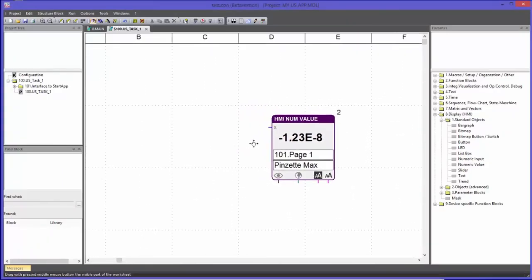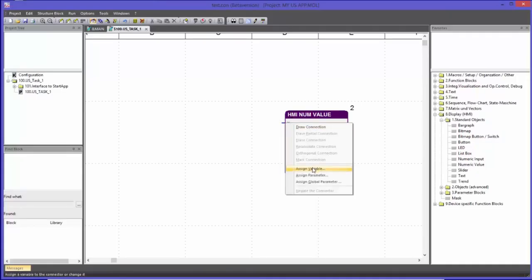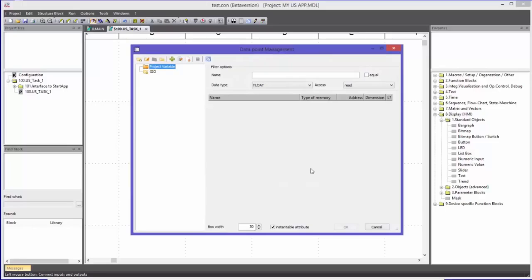I am zooming into the worksheet. This function block is now linked to the graphical object Pinzette Max, which is on mask 101 Page 1. The upper bar always shows the mask in which the object is implemented. Now I will connect the app connector Pinzette Max with the input of this block — that is how I make the connection to the real-time kernel. I will dock an attribute using the command Assign Variable.